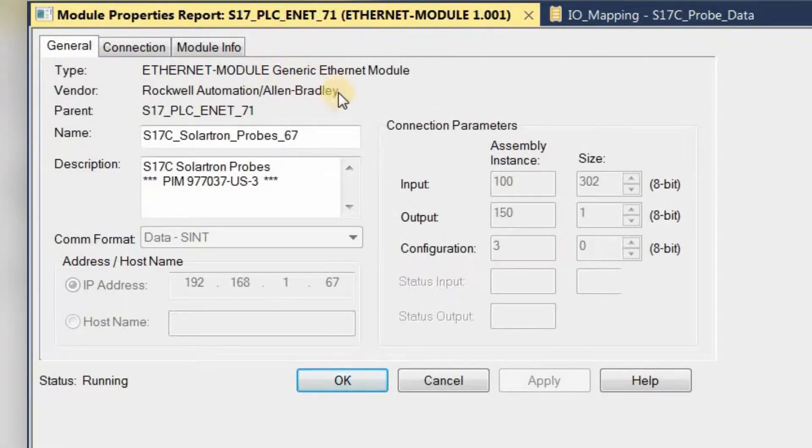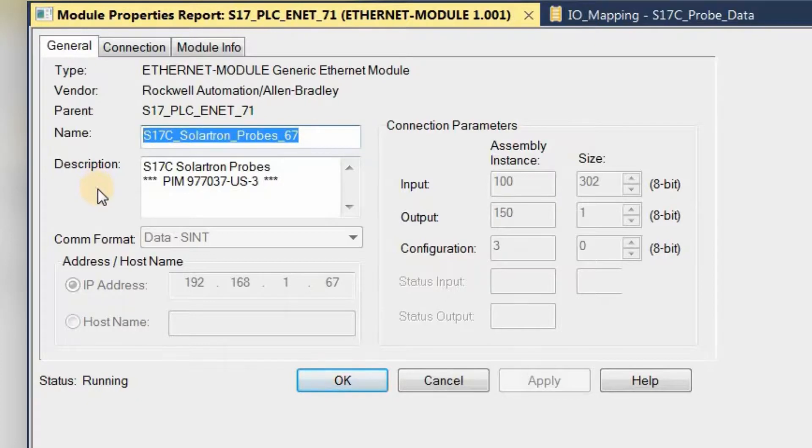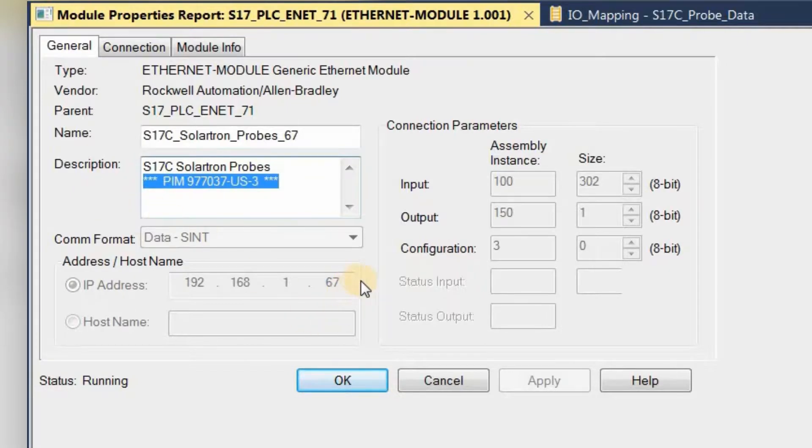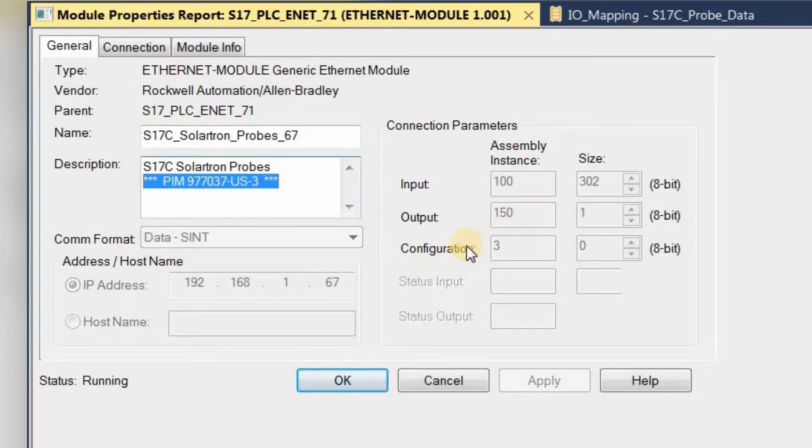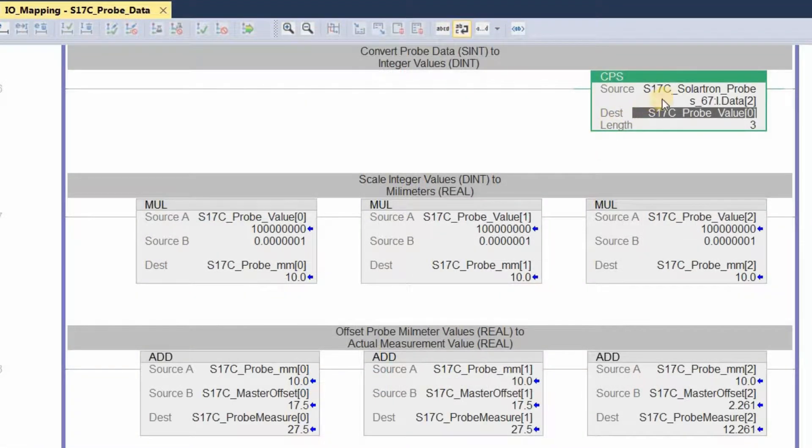Now here's a configuration screen within the setup software for the PLC. Here you have an Ethernet module, generic, and then the name of it is just given S17C, Solartron Probes. This is basically the designated name for the PIM. And if you'll note too, under description, the part number is matched. Also the IP address matches what has been uploaded to the PIM, and then over here you have the connection parameters, namely the assembly instances for input, output, and configuration. Assemblies again are predefined collections of data residing in an adapter.